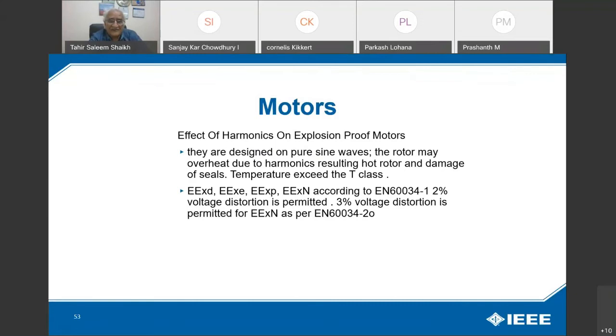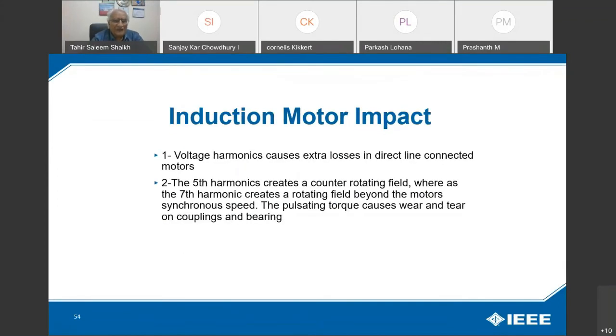For EEx d, EEx e, EEx p, EEx n, according to EN 60034-1, 2% voltage distortion is permitted. 3% voltage distortion is permitted for Ex n as per EN 60034-20. So you have to be very careful when you are using your equipment exposed to the atmosphere. The environment will have too much effect on these components. A voltage harmonic causes extra losses in a direct line connected motor. And for VFD, the fifth harmonic creates a counter rotating field, whereas the seventh harmonic creates a rotating field beyond the motor's synchronous speed. The pulsating torque causes wear and tear on coupling and bearing. The increased use of VFDs creates this type of fault for induction motors.